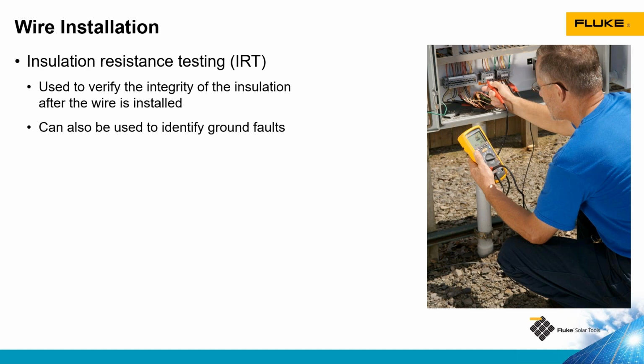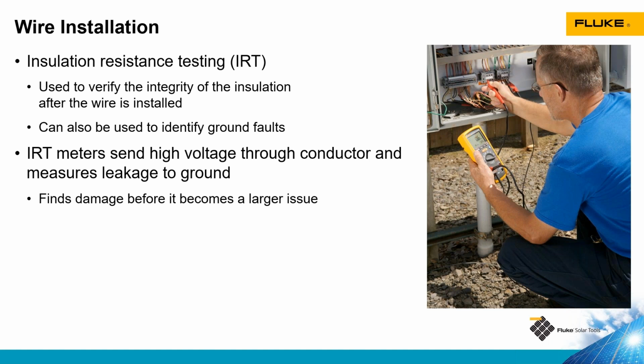We can also use insulation resistance testing to find ground faults. Essentially, what it's doing is sending a high voltage, low current charge through the conductor. The conductor needs to be isolated from any other components and any electrical equipment. And then we're testing to see if there's any current leaking to ground.